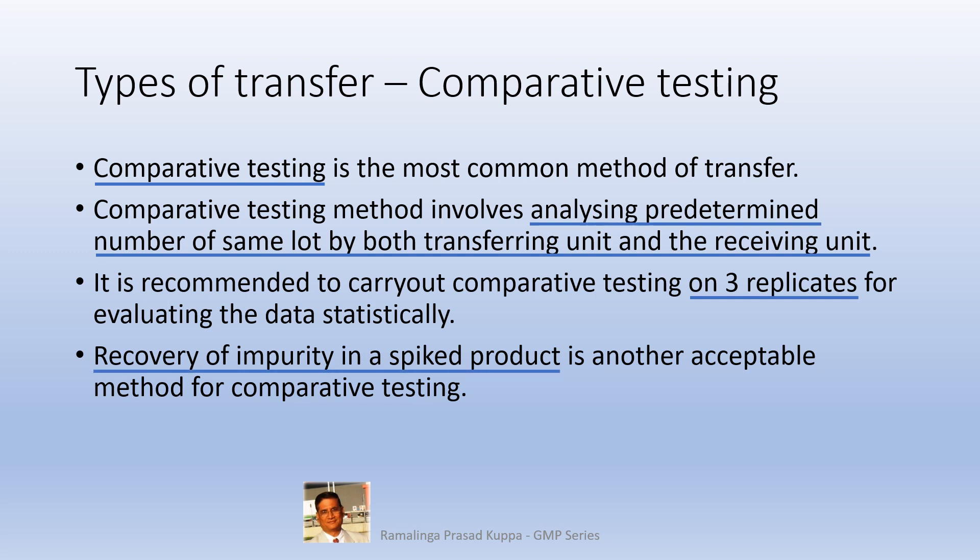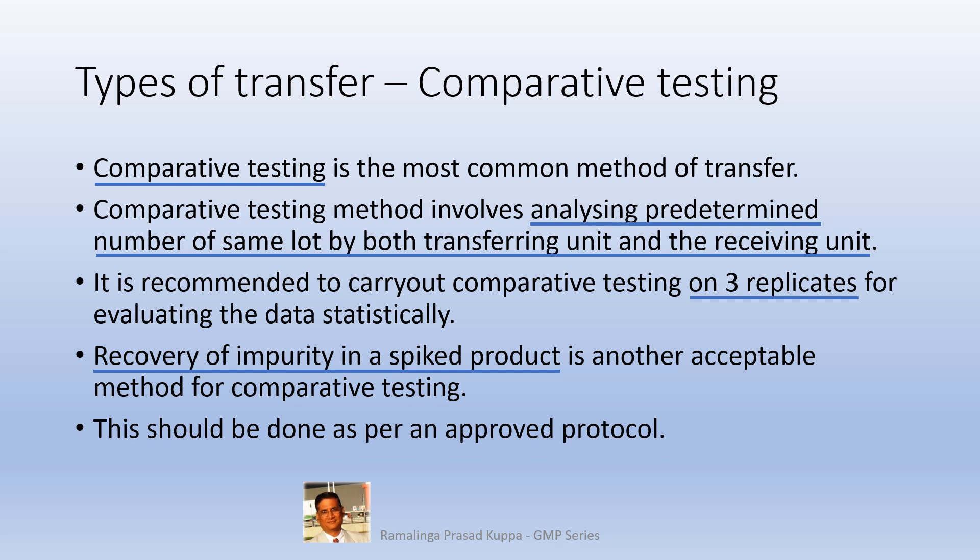Recovery of impurity in a spiked product is another acceptable method for comparative testing. A known concentration of an impurity is spiked into the sample by the transferring unit, and the spiked sample is analyzed at the receiving unit. Recovery means how much percentage of the added impurity is determined. The recovery should be around 99 percent or more, though the recovery percentage varies depending upon the capability of the analytical method. Estimation of statistical variability should also be part of the acceptance criteria, and all these aspects should be addressed in an approved protocol.